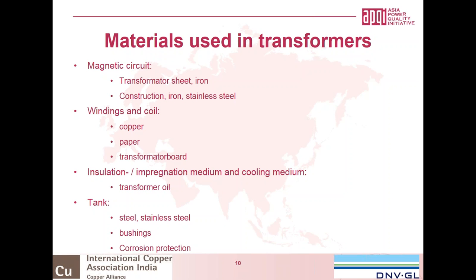For insulation, normally for an oil transformer you will use transformer oil, of course, and for a dry type transformer you will have the air which is used as an insulation, and also of course the epoxy within the transformer which is used. And for the tank around the transformer you will often see that it's made of steel in case you have an oil transformer, and for the transformers which are really high power, very often some parts of it can be used as stainless steel. Of course the transformer has some bushings, and of course, on the outside of the transformer you will need some corrosion protection to make sure that in some areas you don't have corrosion within a certain limited time, and that could influence your transformer.